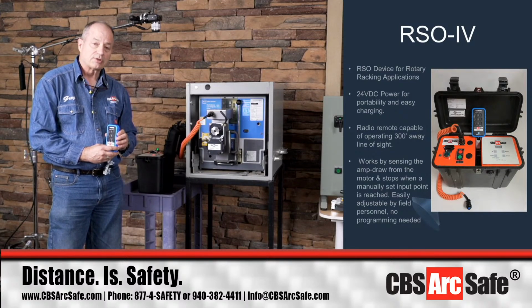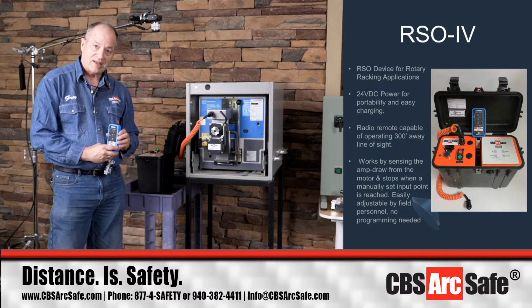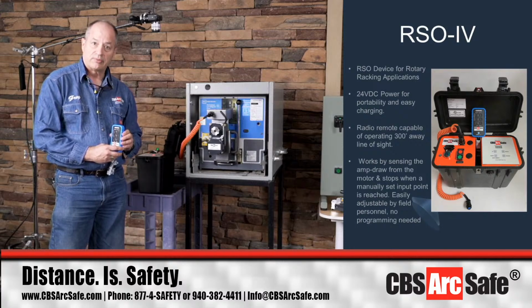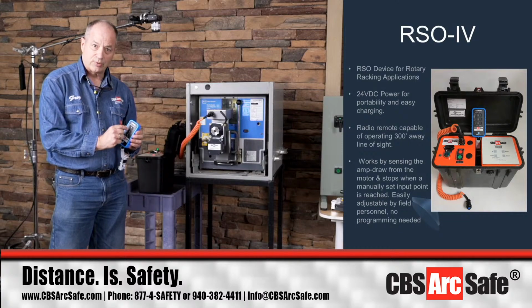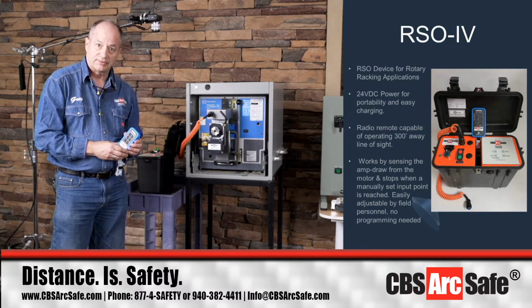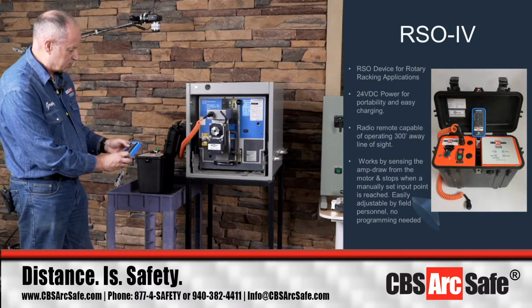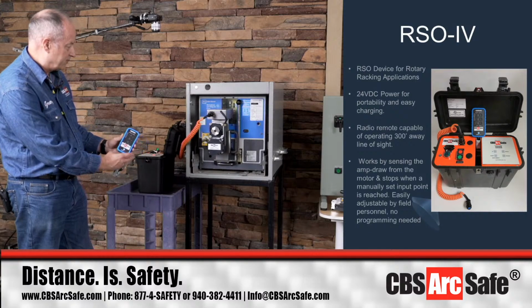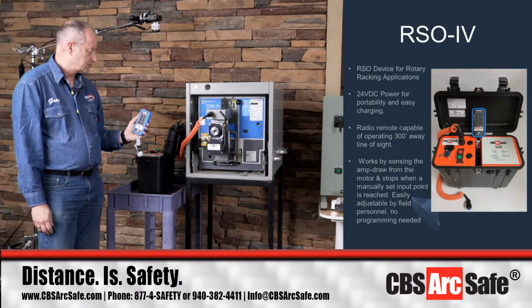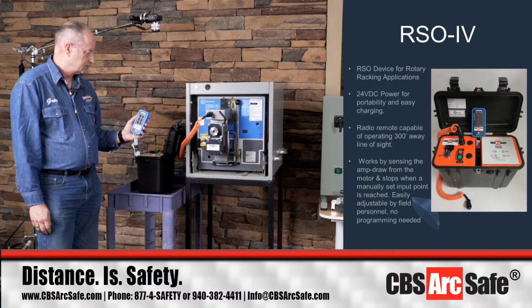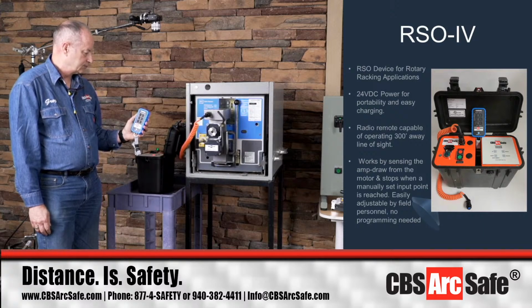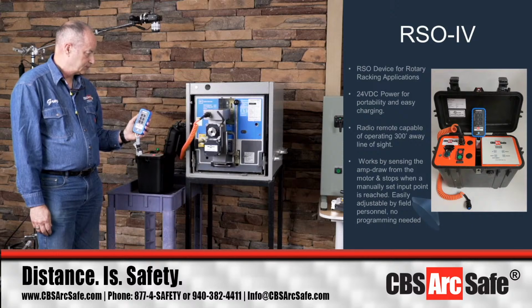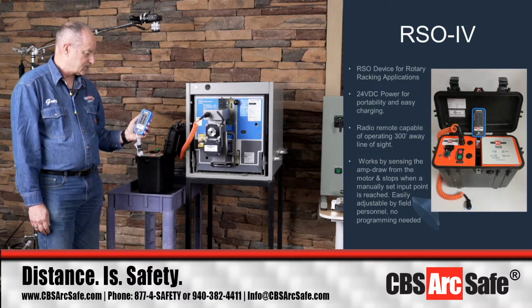If your breakers are located in a metal building and you have to be outside, you're going to have to prop the door open so that you get rid of the Faraday cage effect of your steel building, and you can see that you still have a good operational link between this and the base to be able to rack the breaker safely. So we're in the install position, so we're going to go to remove. We just hold it down momentarily. And that stops it right there.